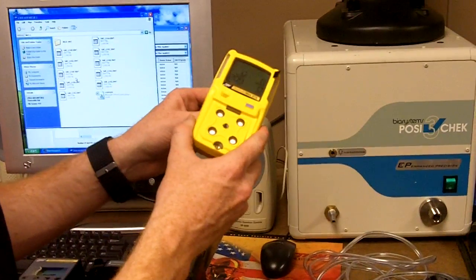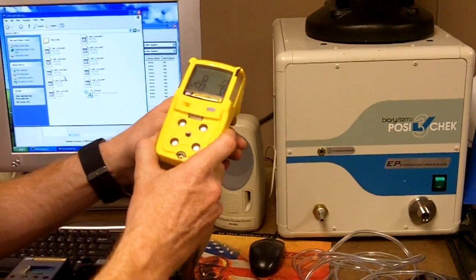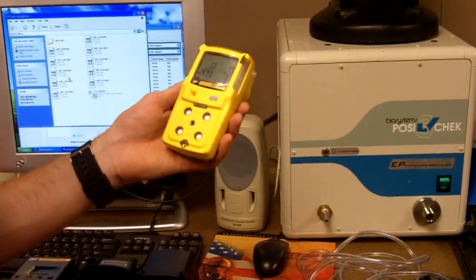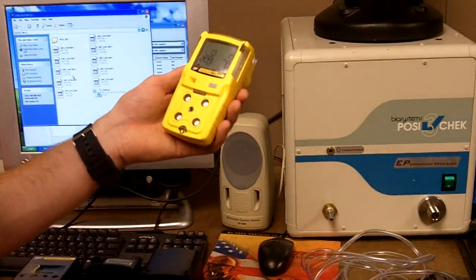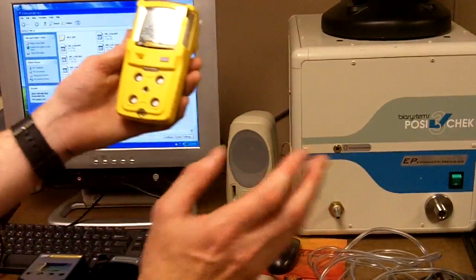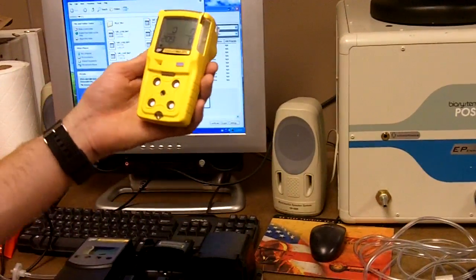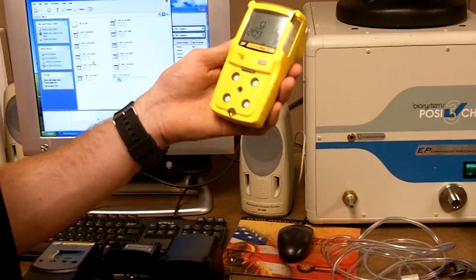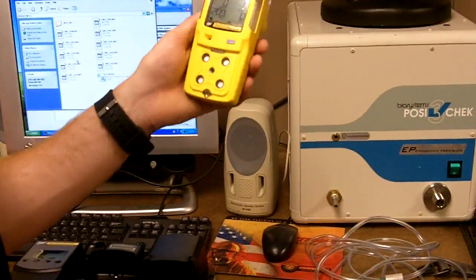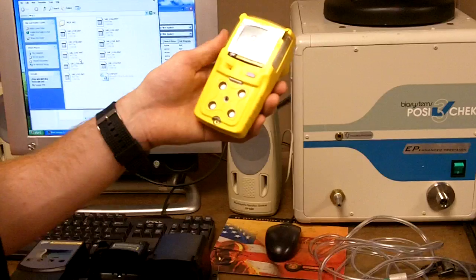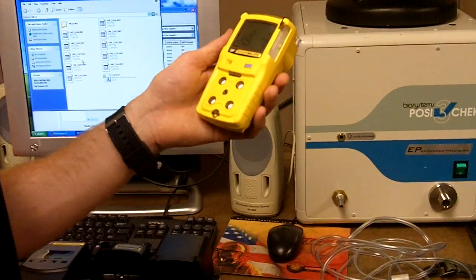rechargeable battery. It does not have the option to be switched out. So once the batteries are shot, you need to charge those. So with our calibration system, we'd be able to not just calibrate it, but it also does a charge. If we needed to charge it in the field and have this one, we could hook that up, or else we could just hook it up to its own power supply.